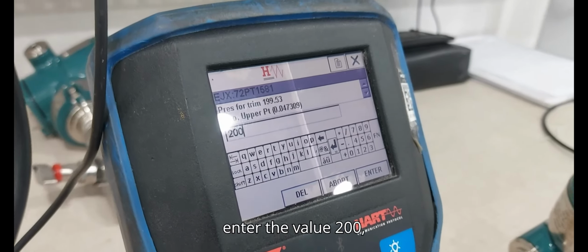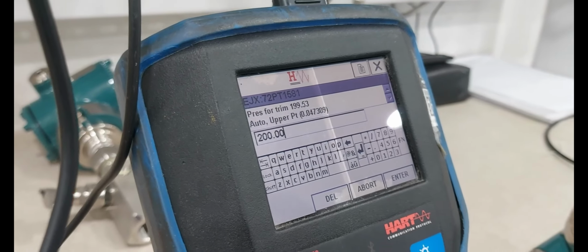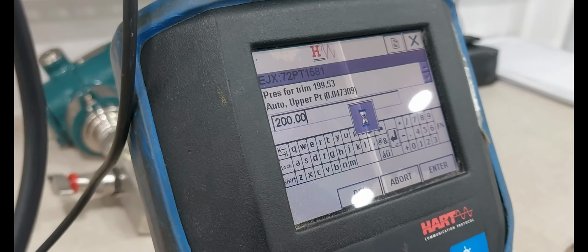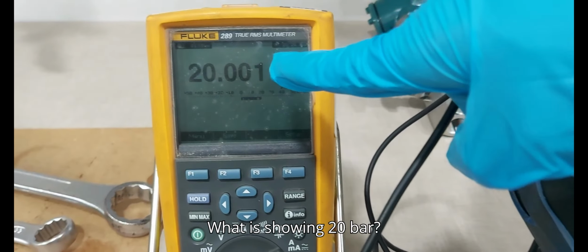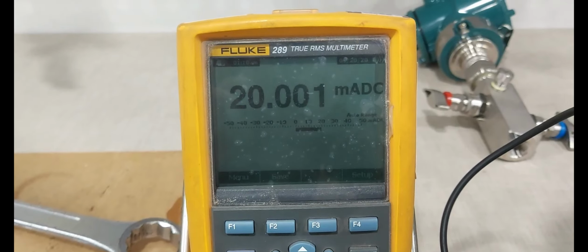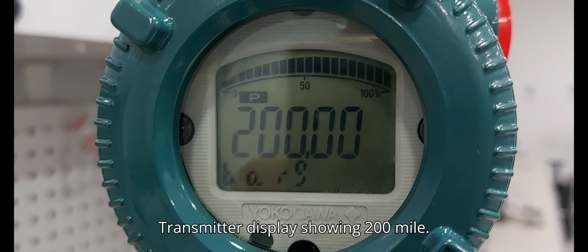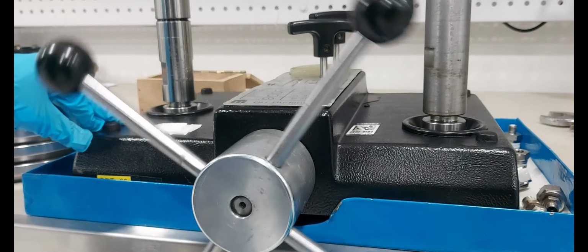Enter the value 200. Enter. Output is showing 20 milliamps. The transmitter display shows 200 bar. The screw pump is rotated counterclockwise.